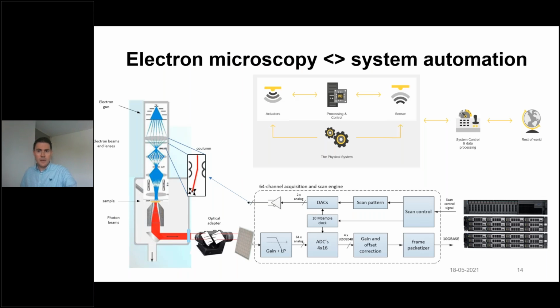So let's have a quick look at the complexity of the electron microscope. On the left-hand side, you see the actual electron microscope itself. So with the electron gun, the beams fall through lenses onto the sample, and the scintillator, which converts the electrons into photons. And that light is then coupled out of the system, out of the vacuum actually, onto an image sensor. And the data from that image sensor is then sampled and processed. First, there are some samples taken together, so we do oversampling there, and we also apply gain and offset corrections on that data set.